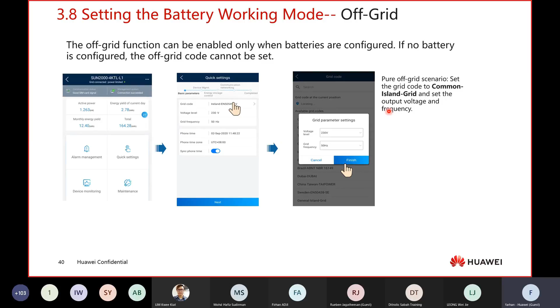So when you do this, you can see the grid code. They have some selections here. You need to select common island grid, which means you can set the output voltage and frequency. Normally the site has a generator there, so you can follow the generator's rated voltage and frequency.